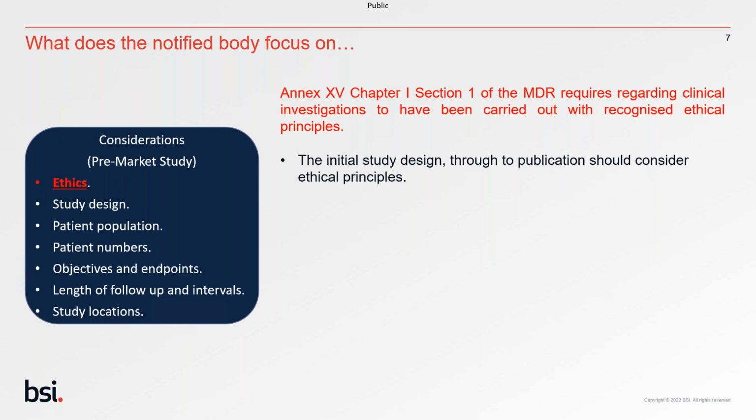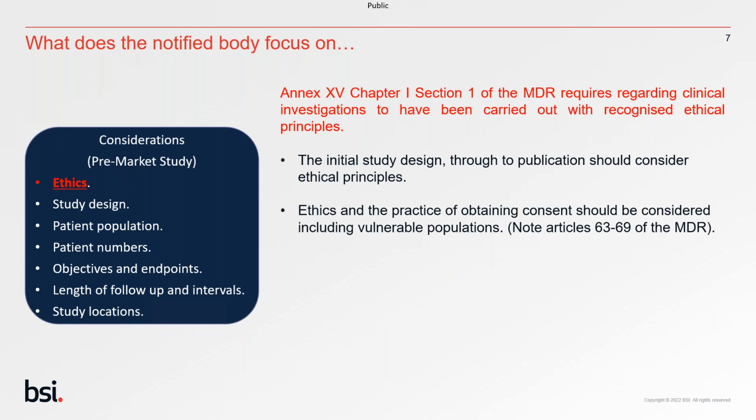The notified body wants to make sure that ethical considerations are given across the whole study to release of results. Ethics and the practice of obtaining consent should always be considered, including vulnerable populations. So if your study design, for example, has included breastfeeding or pregnant women, then we need to make sure that there is documented ethical approval specific to that vulnerable group within your ethics committee submission. It's worth looking at Articles 63 to 69 of the MDR because they highlight those vulnerable populations, and also damage compensation as well.